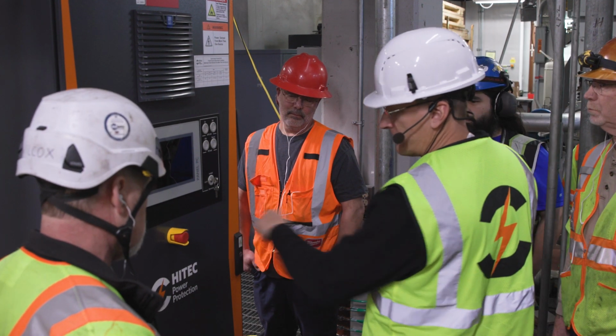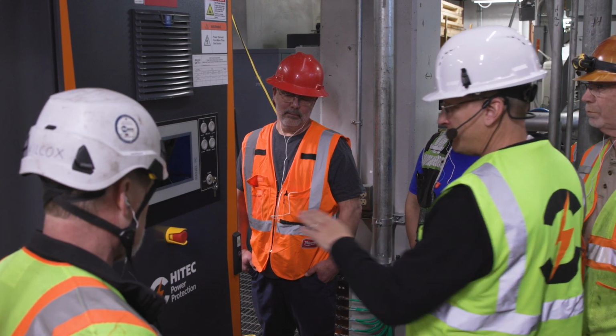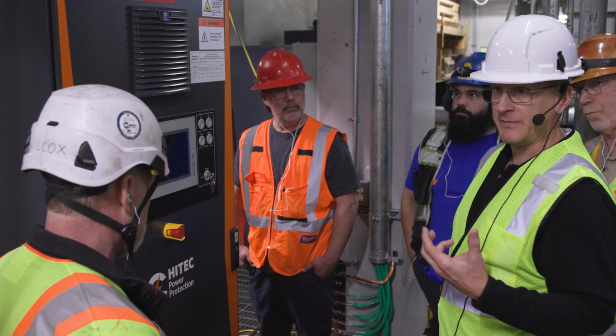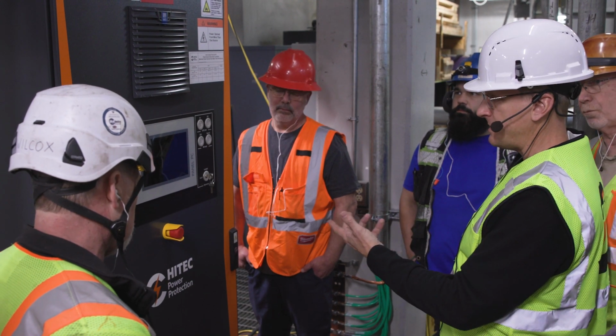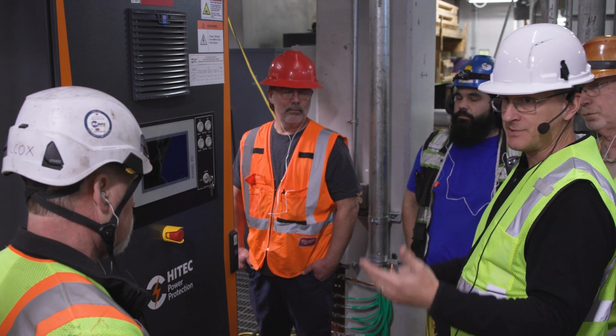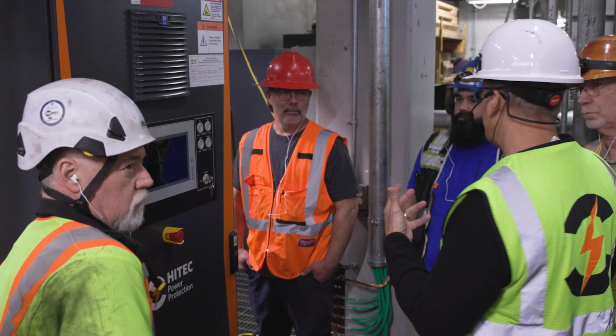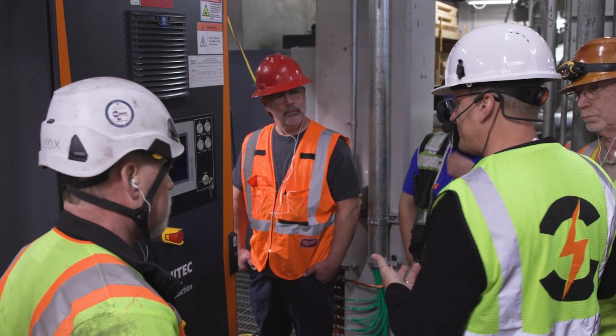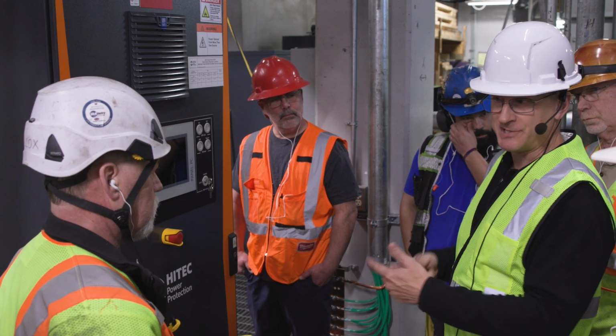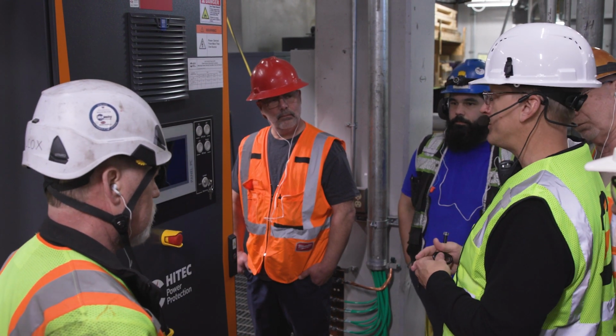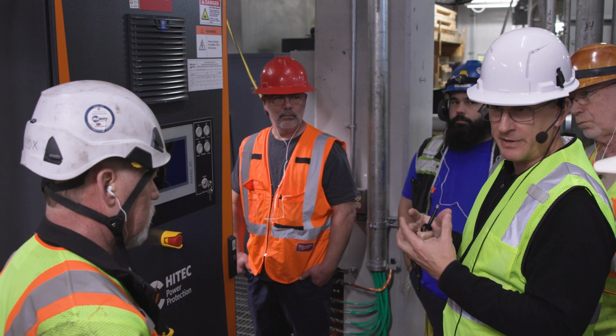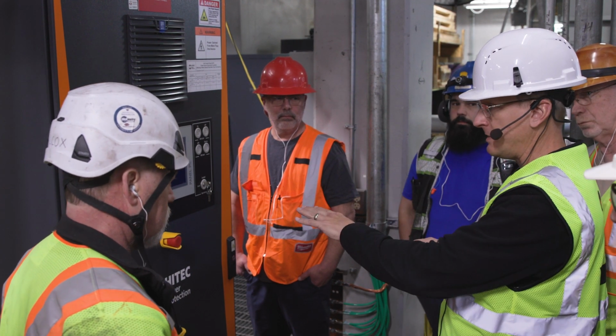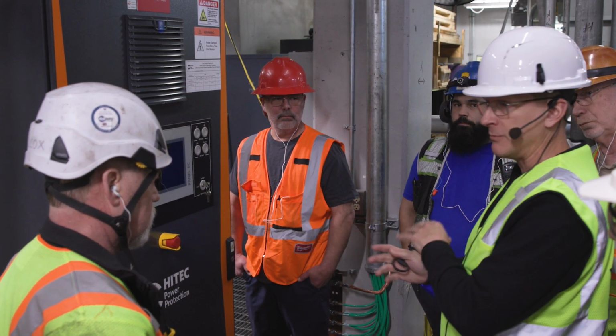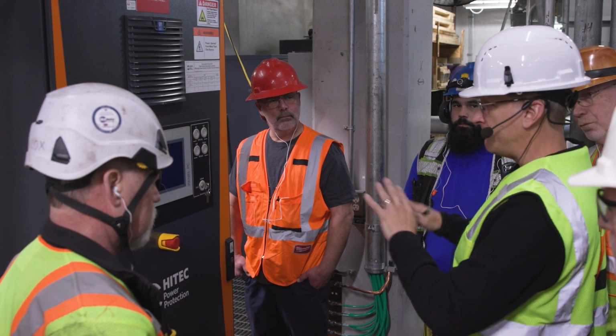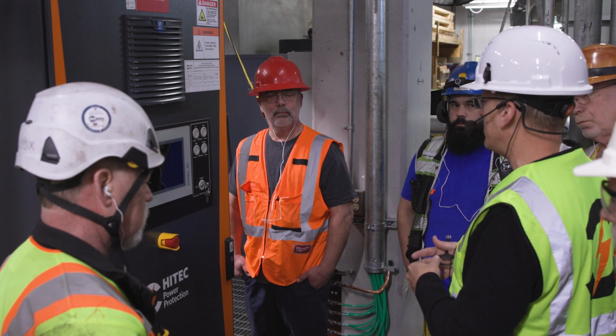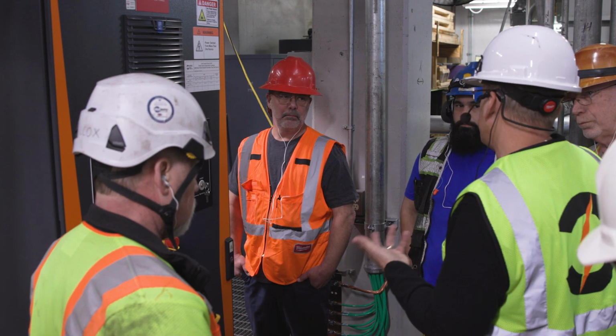And of course you've got your emergency stop button, which you can always press at any time for any kind of unsafe condition. Emergency stop, again, will send the unit to bypass and shut everything down. However, keep in mind that an e-stop action is not going to stop your shaft. Your shaft is still going to be spinning. We have no way to brake the shaft on an e-stop. So it's going to send the unit to bypass, it's going to shut everything down, it's going to remove excitation from the alternator, but the shaft is still going to spin. Just be aware of that. The diesel will also shut down if the diesel is running. Okay.